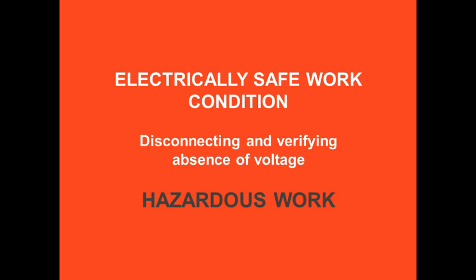But just because you have a perfect lockout tagout program does not exempt you from anything in 70E. You still need to develop a 70E program and make sure we're following the practices for arc flash, PPE, training, and a whole bunch of other stuff we're going to talk about. I always pause here to make sure everyone understands this, because I've had that rebuttal from folks before saying, well, we have a perfect lockout program so we don't need to go through all of this. Not true. Absolutely, they go hand in hand.